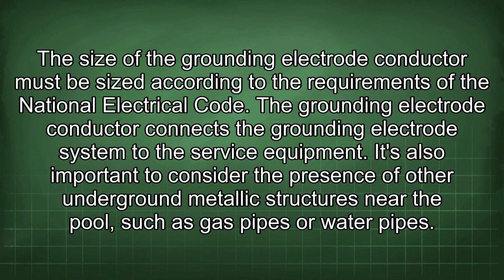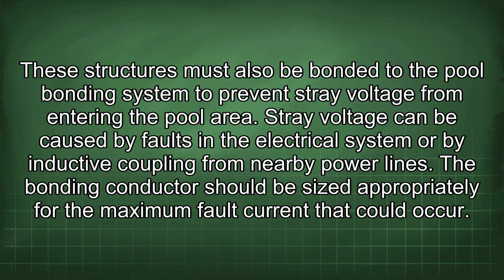It's also important to consider the presence of other underground metallic structures near the pool, such as gas pipes or water pipes. These structures must also be bonded to the pool bonding system to prevent stray voltage from entering the pool area. Stray voltage can be caused by faults in the electrical system or by inductive coupling from nearby power lines. The bonding conductor should be sized appropriately for the maximum fault current that could occur.